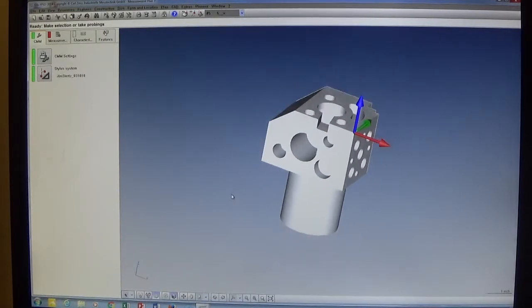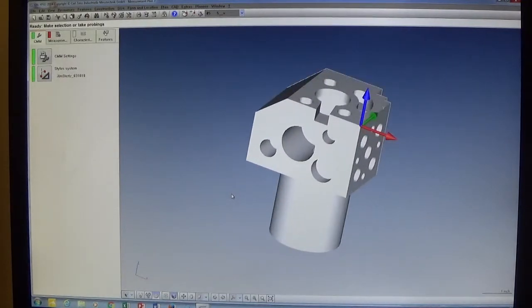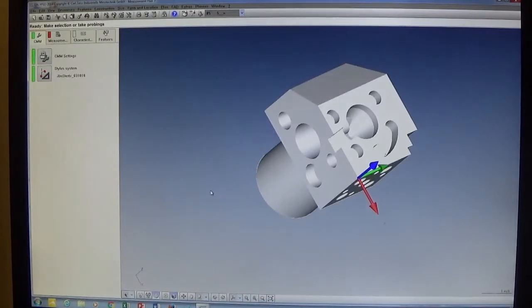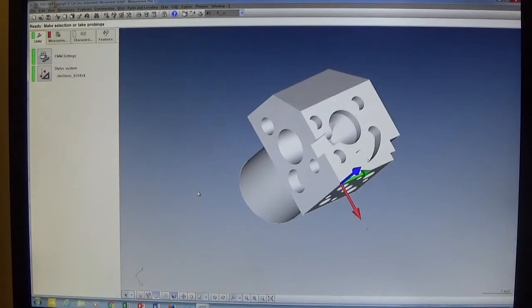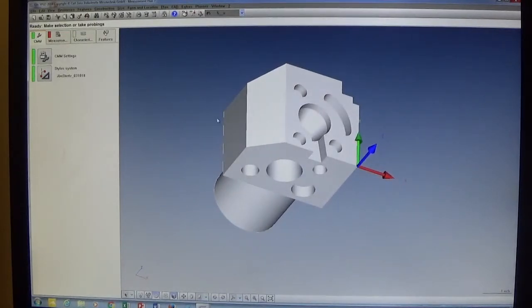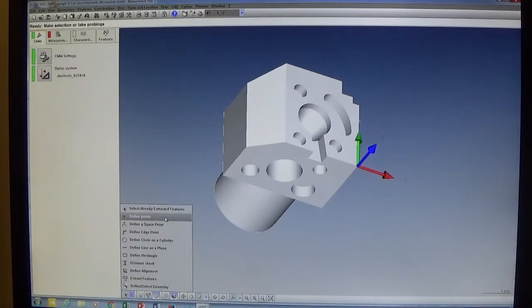To navigate the CAD model: scroll the mouse wheel to zoom in and out, press and hold the right mouse button to rotate, and press and hold the left mouse button to pan. We rotate to see the features we want to measure. In the top menu, the active stylus is currently number five — the last one qualified — so we change it to number one since we'll be measuring with the Z-minus stylus. Then on the bottom toolbar we select the 'Select or Create Geometries from CAD Model' drop-down and choose 'Define Points' to allow us to measure points on the CAD model.